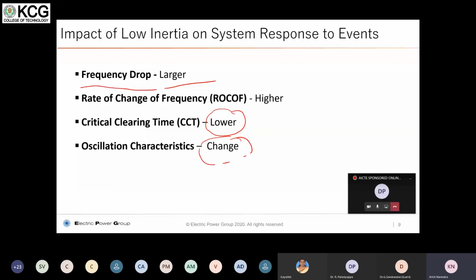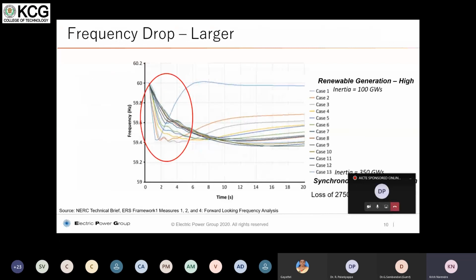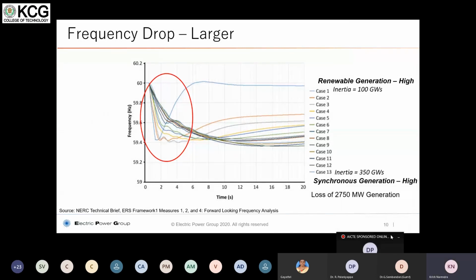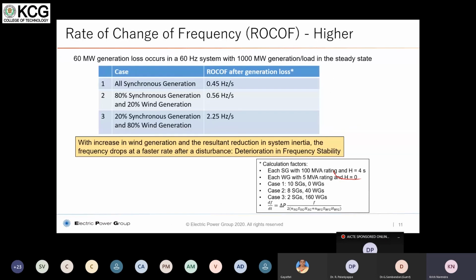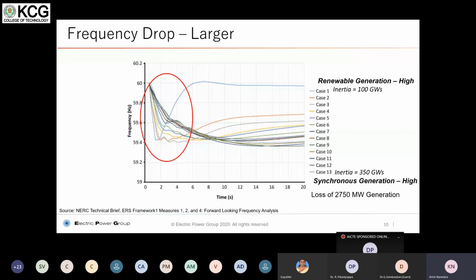Let's take a quick look at each one of them, and how it's going to impact. For example, here, the renewable generation is high in case 1, and in case 13, synchronous generation is very high. So when the synchronous generation is high, obviously you will have better support from inertia. So synchronous generation is high in case 13, and therefore the curve operates in a safer region.